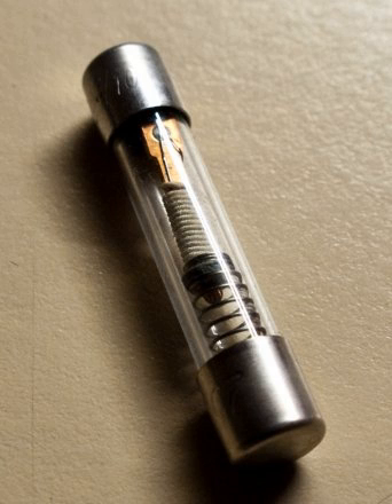While glass fuses have the advantage of a fuse element visible for inspection purposes, they have a low breaking capacity (interrupting rating), which generally restricts them to applications of 15A or less at 250 VAC. Ceramic fuses have the advantage of a higher breaking capacity, facilitating their use in circuits with higher current and voltage. Filling a fuse body with sand provides additional cooling of the arc and increases the breaking capacity of the fuse.